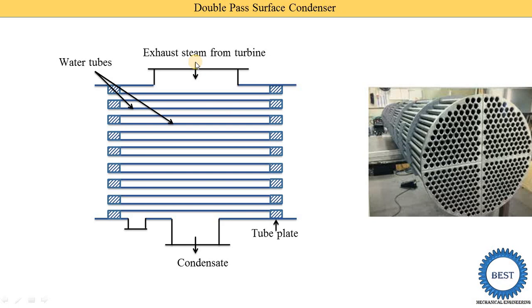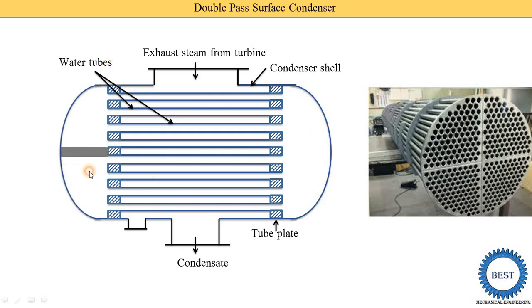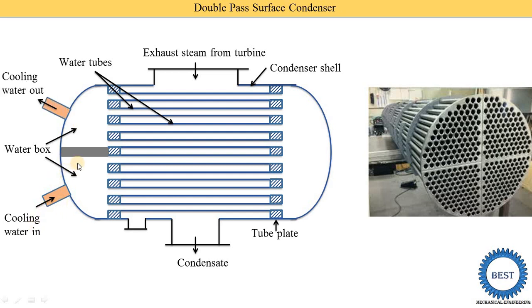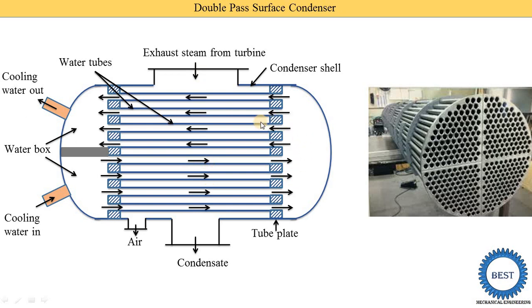Exhaust steam coming from the turbine is supplied into the condenser from the top part of the condenser, and at the bottom we collect the condensate — the liquid form of steam. This is called the condenser shell. Both ends of the shell are covered by using heads. On one head, baffle plates are installed to create the water box. Cooling water is supplied from the bottom of the head and exits from the top, and an air vent is provided to remove air using an air pump.